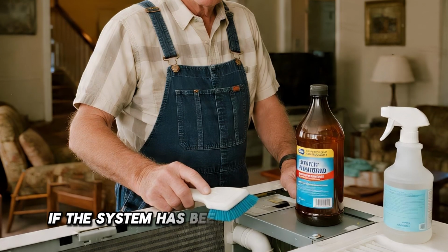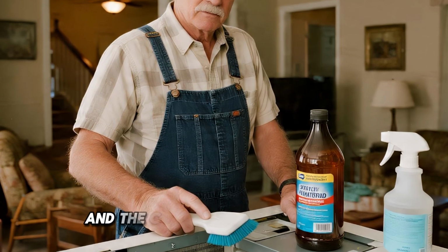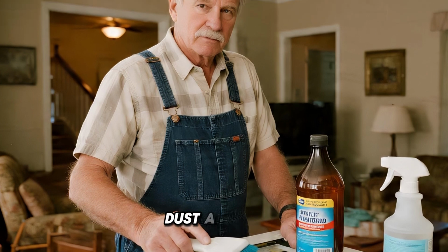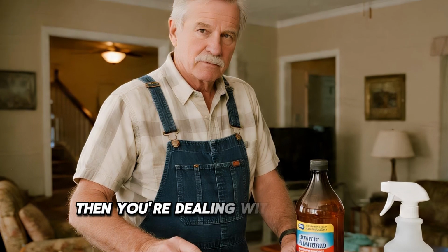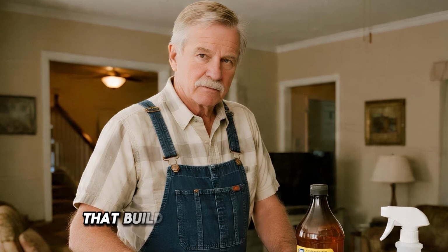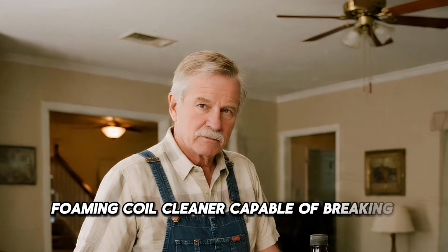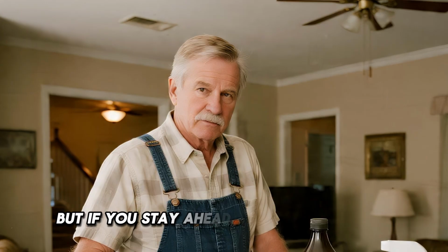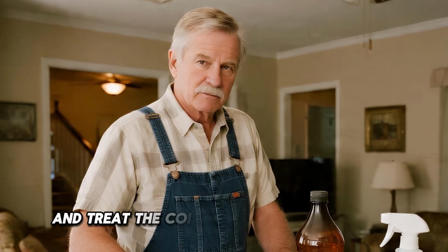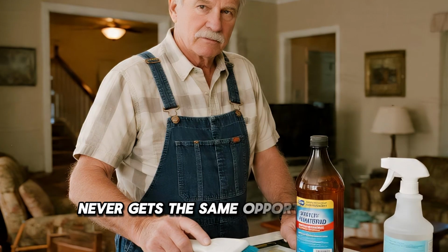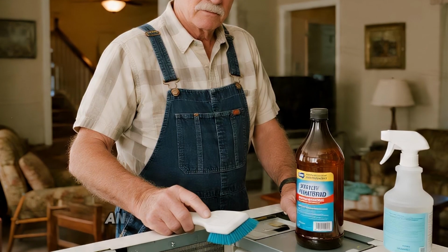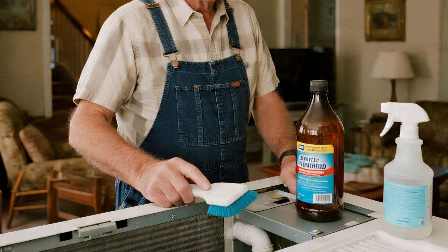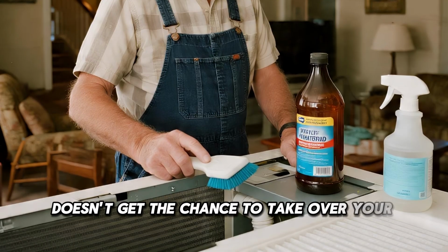If the system has been ignored for a decade, and the coil is packed with grease, dust, and grime, then you're dealing with a different problem. That buildup requires a specialized foaming coil cleaner capable of breaking the bond. But if you stay ahead of the maintenance and treat the coil with peroxide annually, that living layer never gets the same opportunity to establish itself. And that damp gym bag smell doesn't get the chance to take over your house.